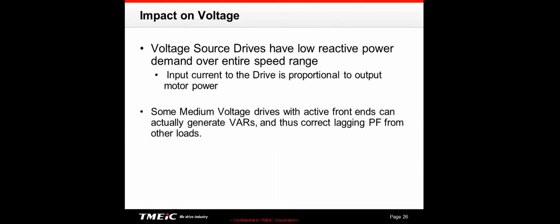Voltage source drives tend to have very low reactive power. And so whether it's low voltage or medium voltage, drives in general have very good displacement power factor. Now, some medium voltage drives, I don't know any low voltage drive that can do this, but some medium voltage drives with an active front end can actually supply VARs. So if you have a low power factor and you put in a certain type of medium voltage drive, not only can it run the motor for you, but it can also regulate your power factor, and it can provide VARs back into the system in order to compensate for other loads and bring your power factor on your system up. So, and that kind of comes free. Anything that you don't need to go to the motor, you can use to correct for power factor.